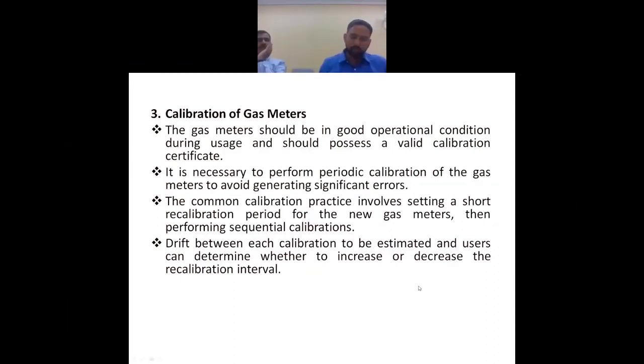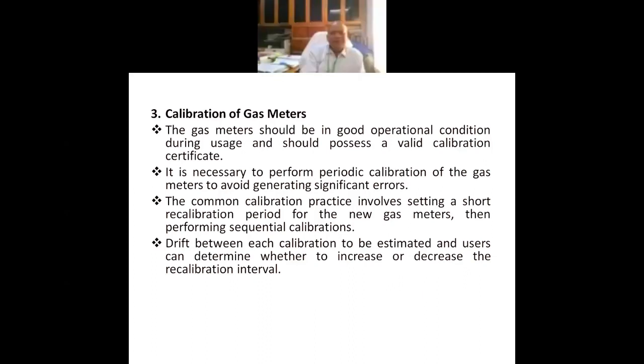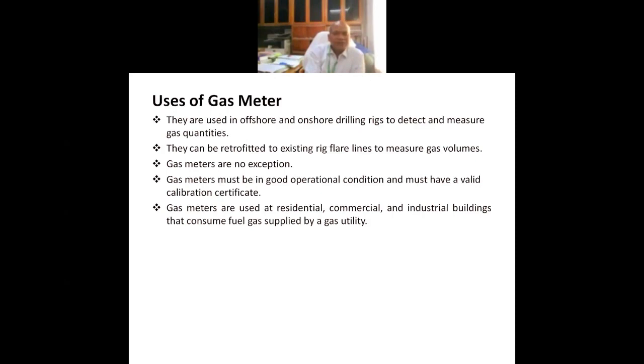Calibration of gas meters: the gas meter should be in good operational condition during usage and should possess a valid calibration certificate. It is necessary to perform periodic calibration of gas meters to avoid significant errors. The common calibration practice involves setting a short recalibration period for new gas meters, then performing sequential calibration. The drift between each calibration is estimated, and users can determine whether to increase or decrease the calibration interval. Gas meters are used in offshore and onshore drilling rigs to detect and measure gas quantities.